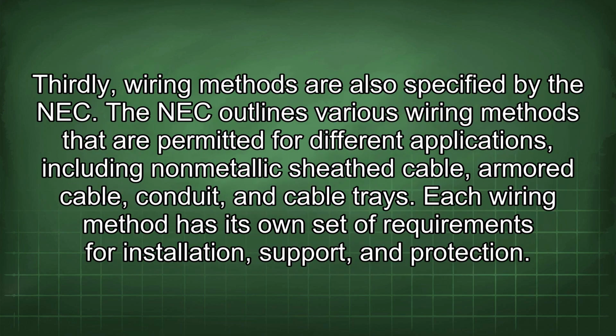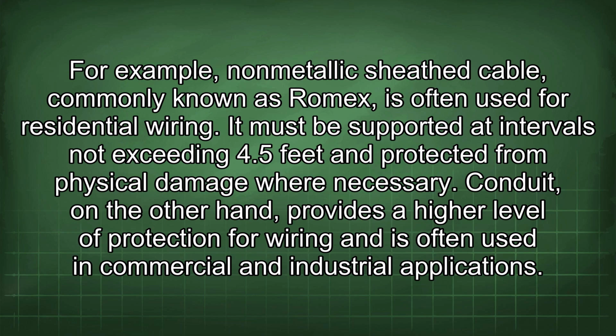Thirdly, wiring methods are also specified by the NEC. The NEC outlines various wiring methods that are permitted for different applications, including non-metallic sheathed cable, armored cable, conduit, and cable tray. Each wiring method has its own set of requirements for installation, support, and protection. For example, non-metallic sheathed cable, commonly known as Romex, is often used for residential wiring. It must be supported at intervals not exceeding 4.5 feet and protected from physical damage where necessary.